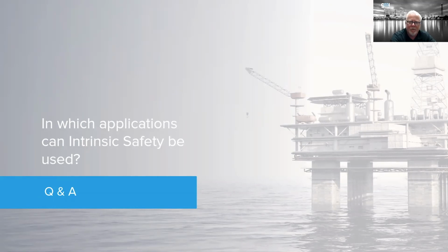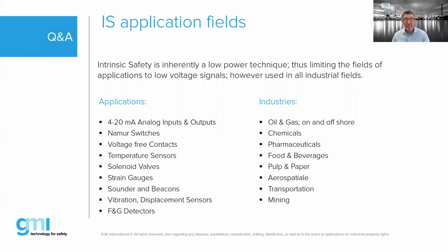Okay, so we have a question which I think is also responding to some of the other questions we have here. In which application can intrinsic safety be used? I think that was one of the poll questions. It's all low power applications. So we have 4-20 milliamp switches, voltage free contacts, temperature, those small solenoid valves, because the maximum energy you can send is 40, 50 milliamp. Strain gauges, sounder beacons, vibration, fire and gas. But it's used in a lot of industry.